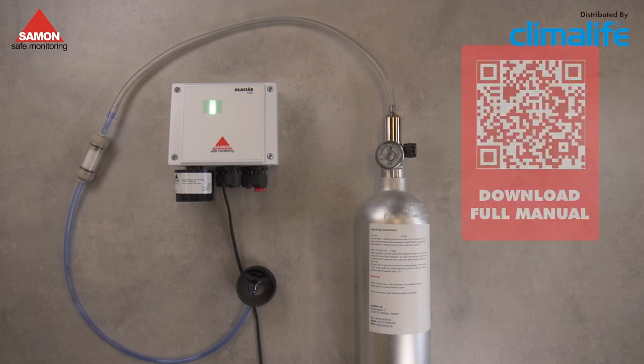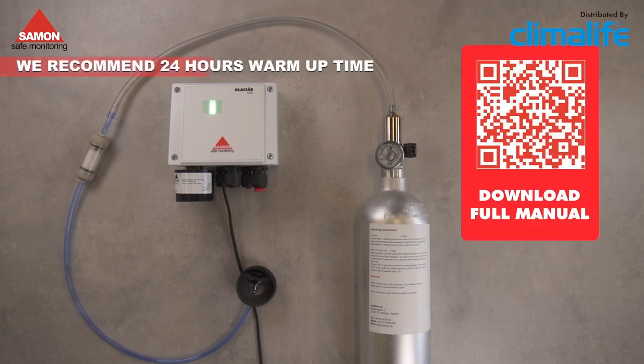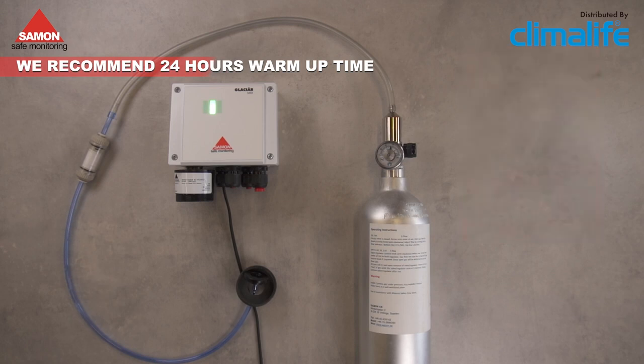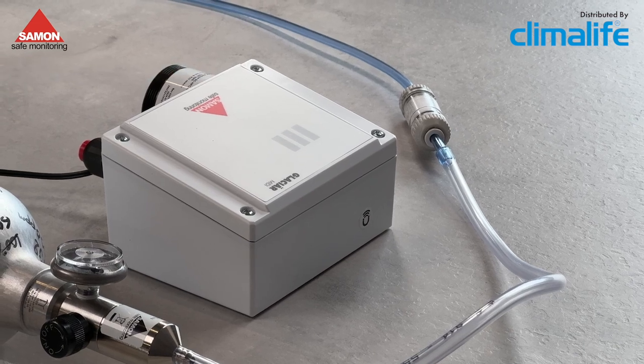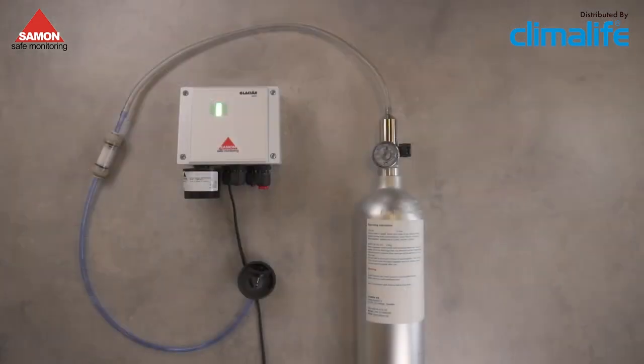Make sure the sensor is warmed up completely. We recommend that the unit has been in operation for a minimum of 24 hours before conducting this procedure to ensure that the sensor is calibrated correctly. Let's have a look at how easily this can be done.